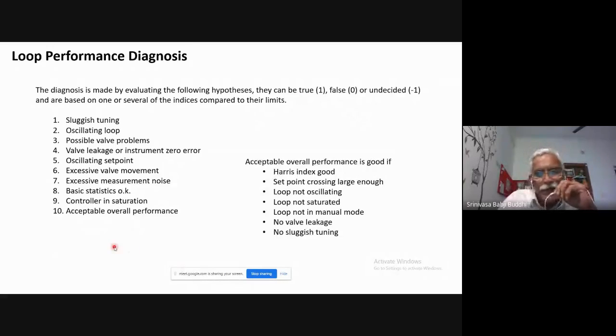For example, if you want to say that the loop is acceptable, that its overall performance is okay, that is possible only if the Harris index is good, the set point crossings are large enough, the loop is not oscillating, not saturated, not in manual mode, the control valve has no leakage, and there is no sluggish tuning. So by evaluating all these hypotheses based on the numerical values obtained from the indices that I've calculated, we come to the conclusion. Okay. So this is how the diagnosis is usually carried out.